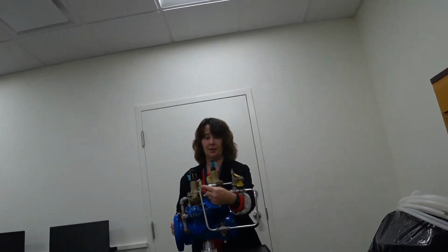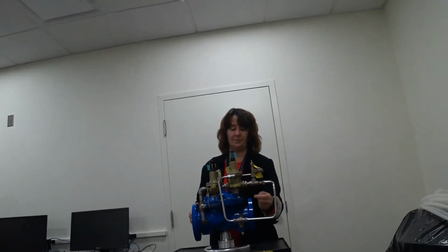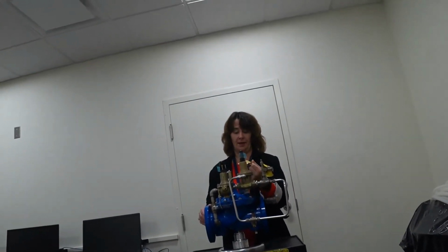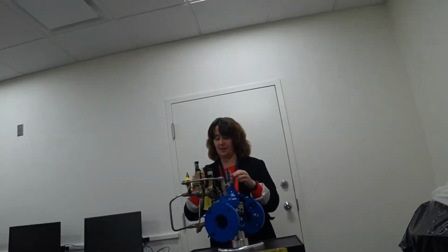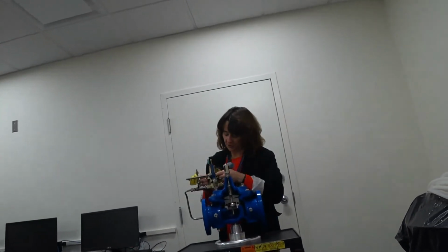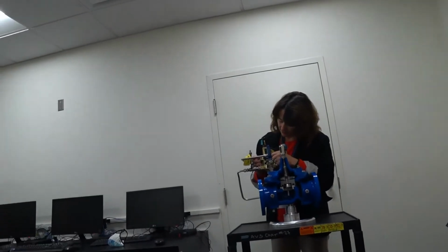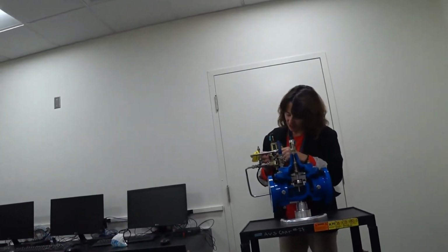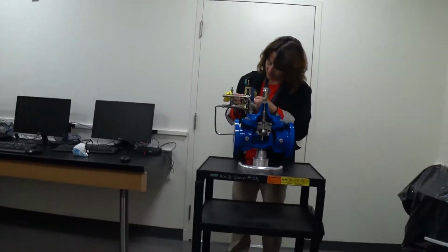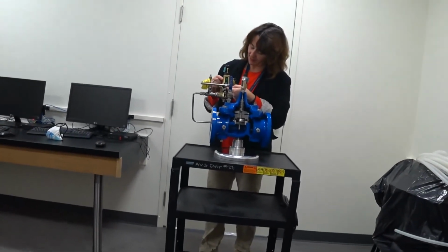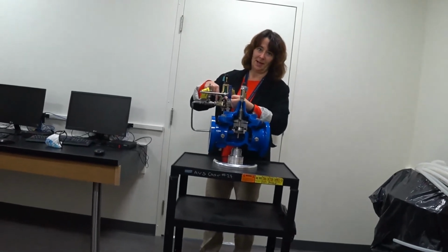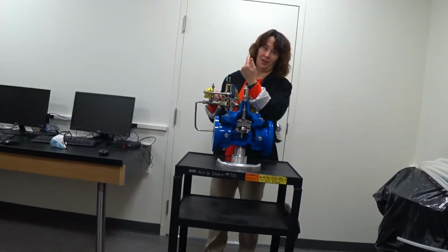That 120 psi is transmitted into this chamber here. And if you guys have looked at the inside of the CRL, you'll notice it's got a valve sensing pressure chamber here. So basically that pressure is submitted to the underside here, and it fights against the spring here. The spring wants to push the stem down, the pressure wants to push it up.